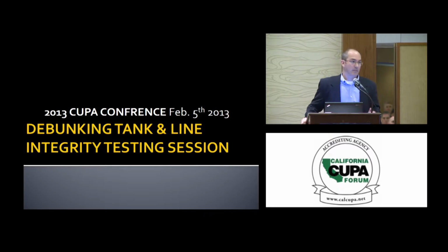So the false alarms had to mean that when you're testing a tank without a leak, this bell curve, which is represented by blue, the line that goes past the threshold right around here, the number of tanks that gave you a leak result higher than 0.05 gallon per hour had to be less than 5% of the tanks you tested. And then on the tanks that were leaking, this other bell curve that's going to give a quantitative leak rate of 0.08 gallon per hour, 0.12, or 0.1, something like that. You had to have 95% of them that gave you an answer that was over the threshold of 0.05.